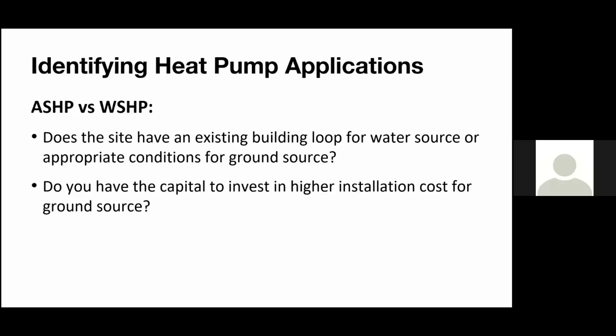So really in those cases, we're comparing an air source heat pump with a geothermal water source heat pump, also known as a ground source heat pump. So the ground source heat pumps are the only way, or almost the only way, to make it all electric and not need a boiler: to have that water go through the ground or through a body of water, like a lake or something like that.